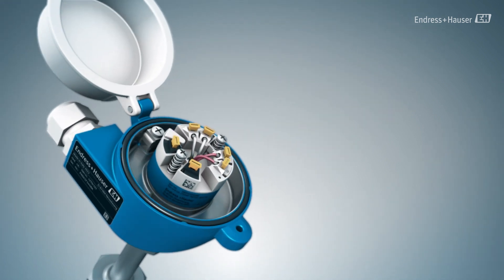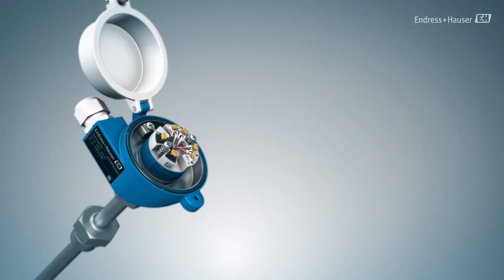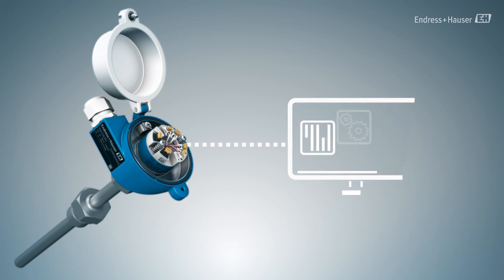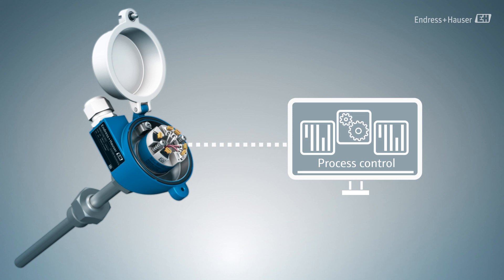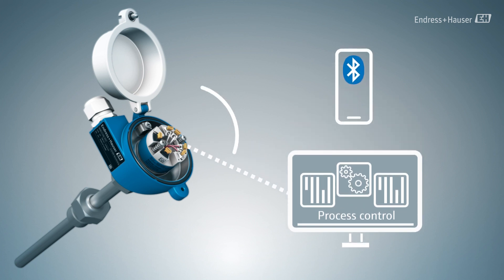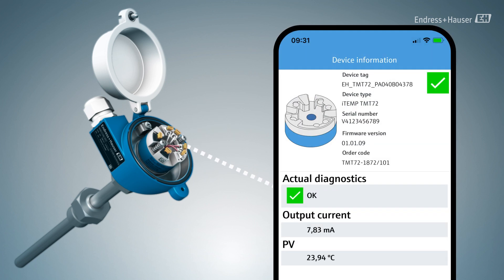The transmitter is the interface between the various sensor elements in the thermometer and the higher-level system for process control, as well as the asset management system. Typical communication signals are 4 to 20 mA, HART, or various digital protocols. In addition, the configuration, observation and troubleshooting of the transmitter can also take place directly in the field via Bluetooth technology with mobile devices.